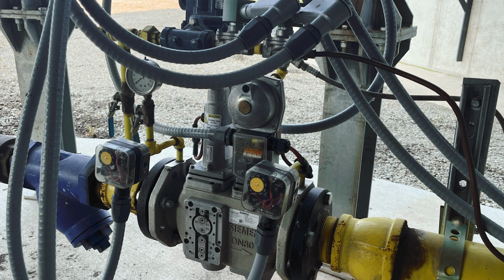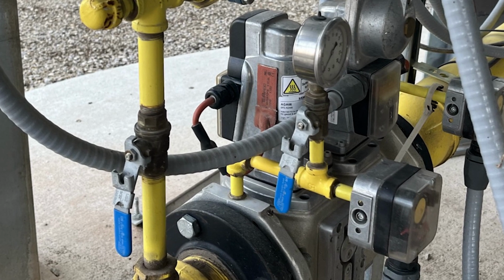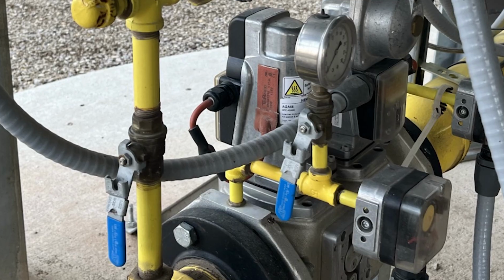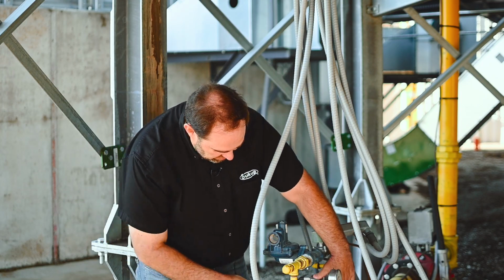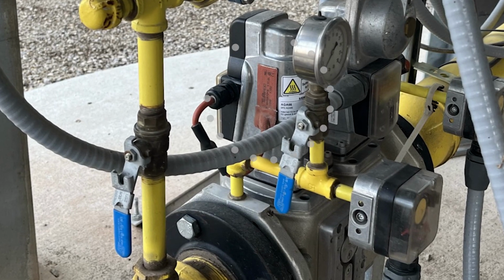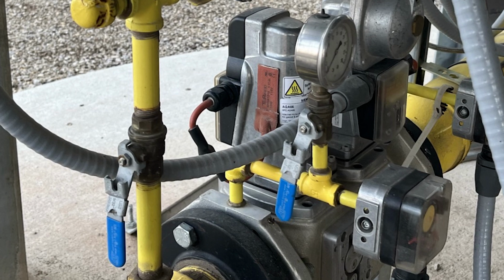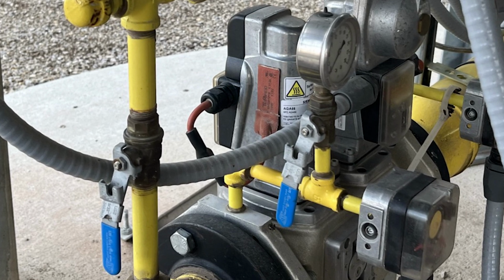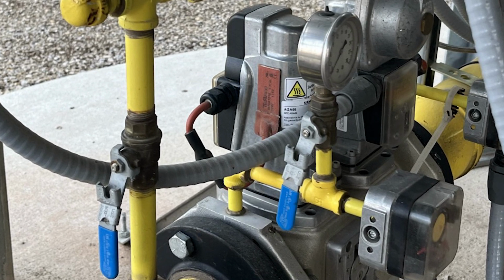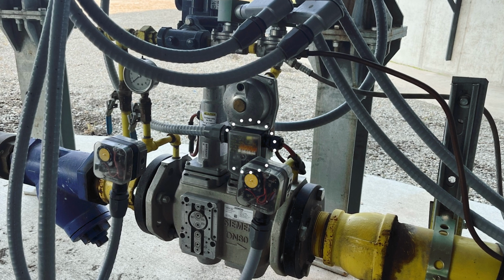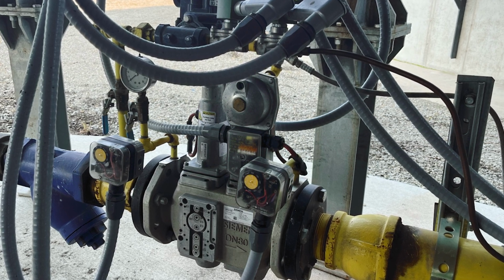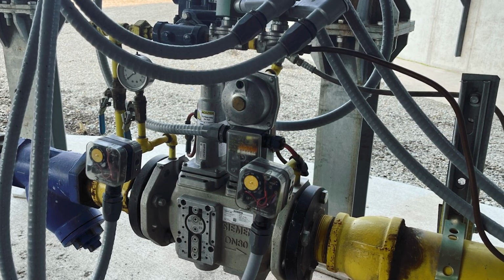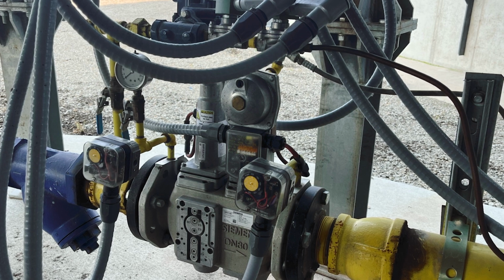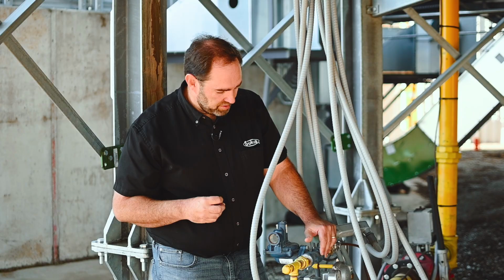The first one is simply an on-off valve. They're an electric over hydraulic type of valve, so there is hydraulic fluid in them. You'll see an orange heater strip on them. That's just to keep the hydraulic fluid warm enough to flow when it's below freezing or very cold outside. The first one is that. On the back side, you'll see a proof of closure switch. As part of the safety circuit, the burner controller needs proof that that valve is actually closed, so we know we're not putting raw gas up there before it starts.